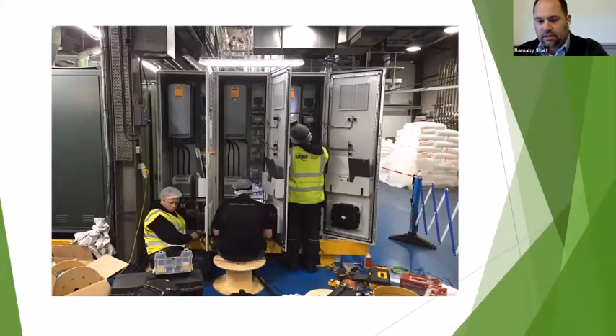These are Parker 690 drives, but we tend to configure Yaskawa, Nidec, or any similar manufacturer. We used encoders on this one for precision feedback. Not on all applications do we use feedback. Some new extruder manufacturers will go open loop without an encoder. It's better with an encoder because you get the performance and the low down torque.